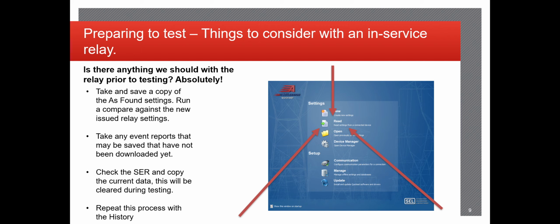The SER is kind of the same idea with more in-depth analysis of the relay elements. The events report pretty much says something happened, and the SER says something happened, these were the elements that picked up and the outputs that operated. The SER is always going to be cleared before testing because you provide the SER data to the client during every test, so you don't want 200 lines of SER data that doesn't even apply to what you're doing. The history is the same idea, everything that the relay may have done while it was in service. This is all stuff that you absolutely want to do before you even think about plugging in your test equipment.